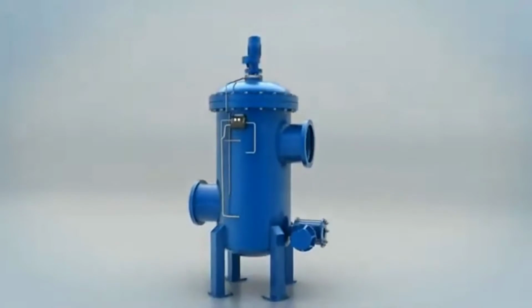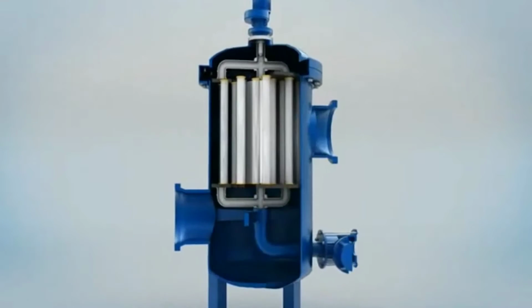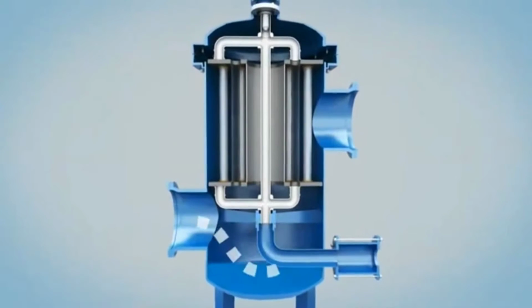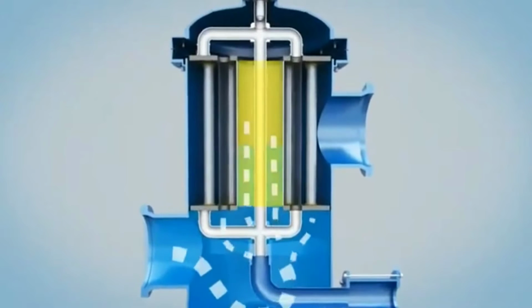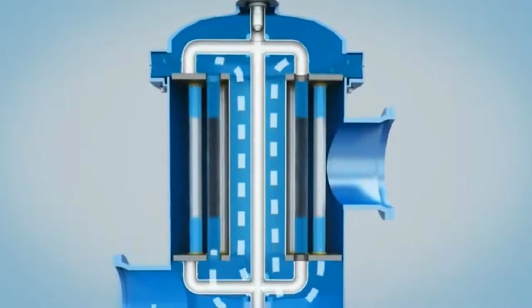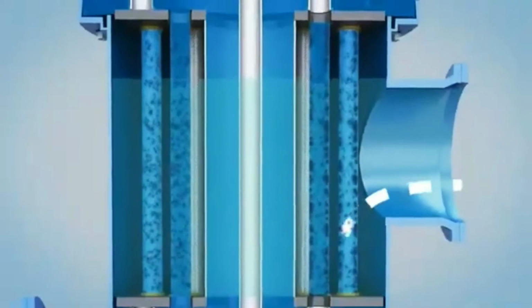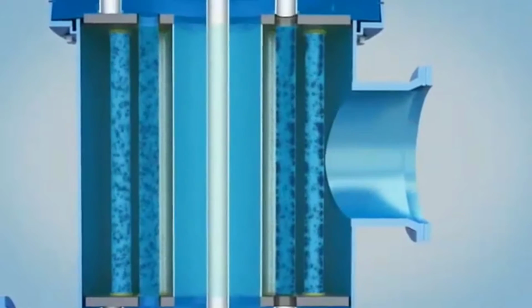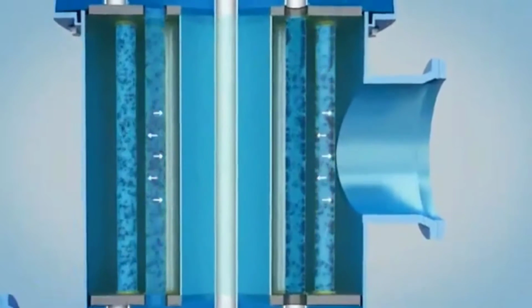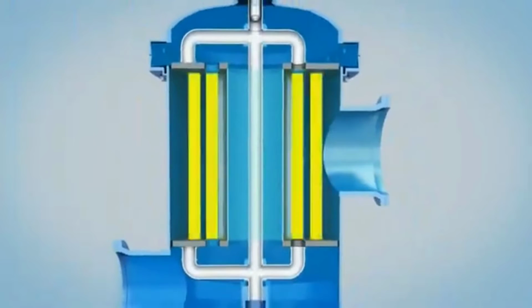During the ballasting process, ballast water should flow through an automatic back-flushing filter first, after the ballast pump. During filtration, seawater flows into the filter housing via the inlet flange. Some of the unfiltered water flows into the upper section of the filter by the vertical tube between 2 filter mesh inserts, and reverses to the filter mesh inserts. This means that the water flows into the filter inserts from opposite directions, then organic and inorganic particles larger than 50 micrometers are separated inside the filter candle, and clean ballast water flows out through the outlet of the filter. When the pressure drop between the inside and outside of the filter mesh rises to a set value, the filter can operate the back-flushing process automatically.